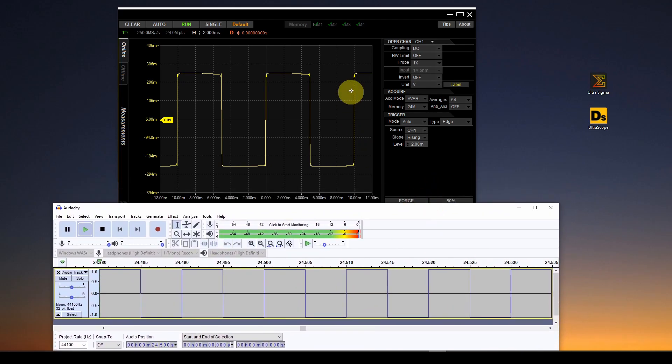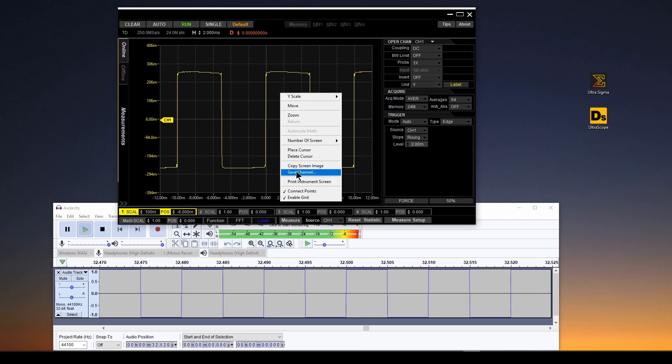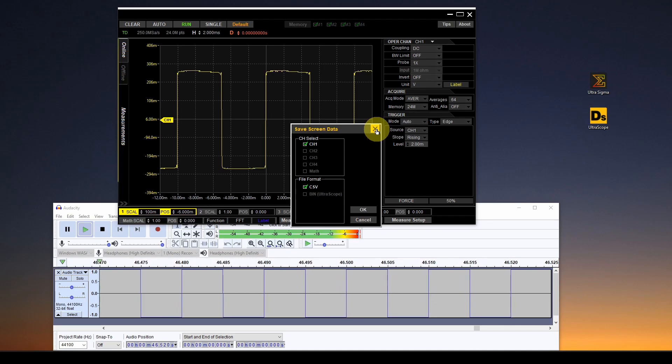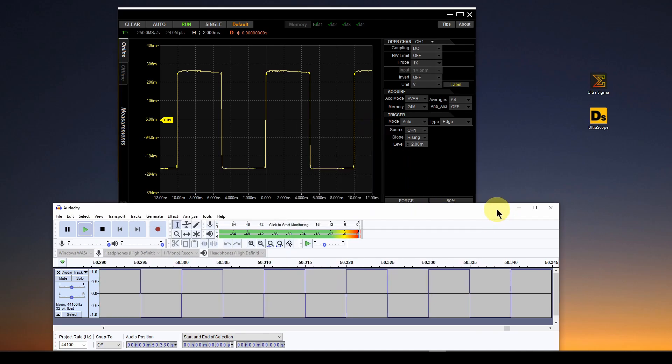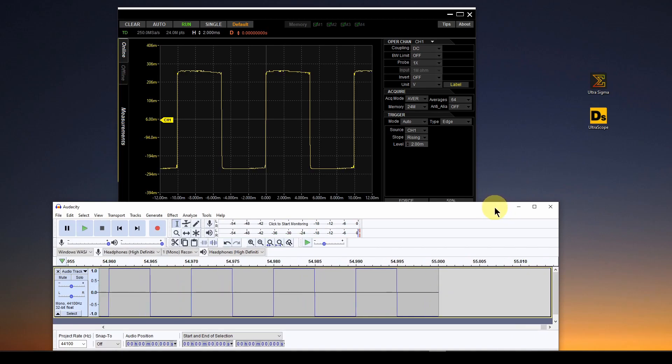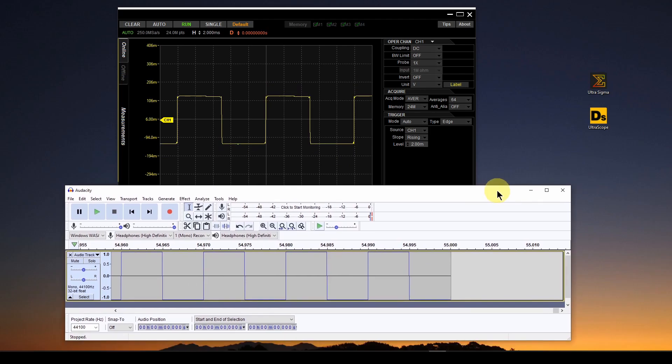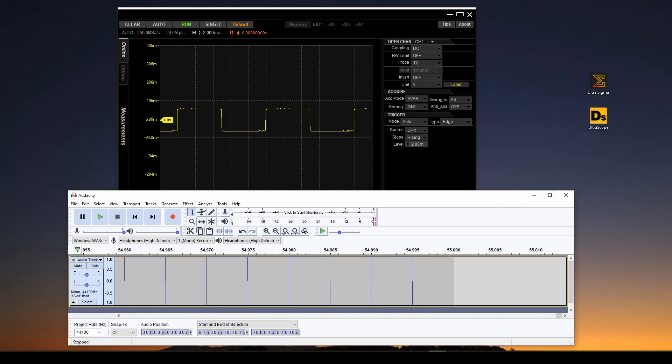And one of the cool things I can do right away is I can right click on this display, and I can go to save channel. And what that does is it will save what you see on the screen, all those samples as points in a CSV file. So I can go save channel, and it's got channel one, I want to save as a CSV. And if I hit OK, I can specify where to put it, and it will save it as a CSV file. And then what I can do is I can reproduce that in Excel or whatever, and I have all that data and I can just manipulate it or do whatever I want in Excel or any other software with it. So that's the basics of connecting to your scope via LAN.